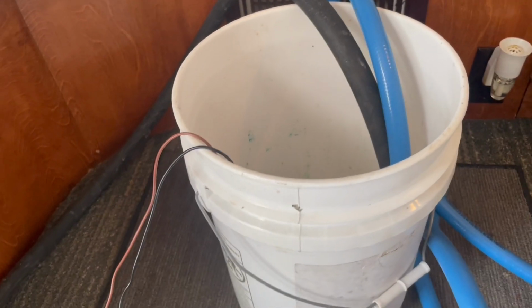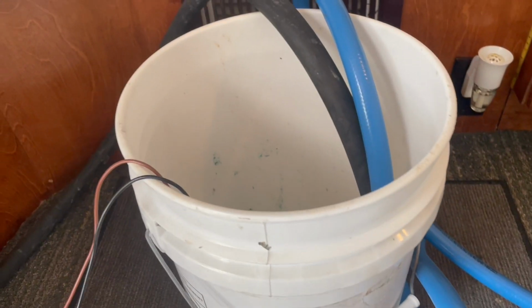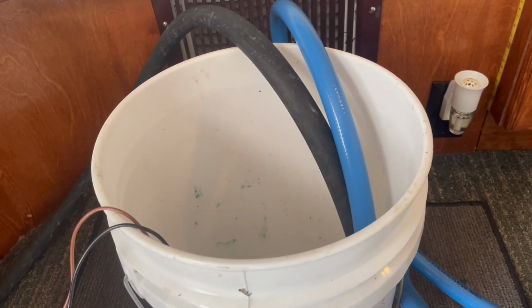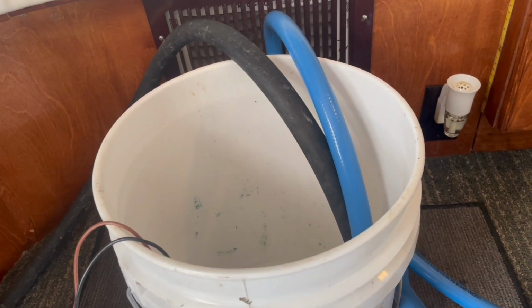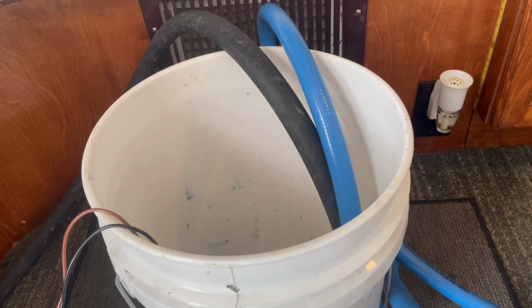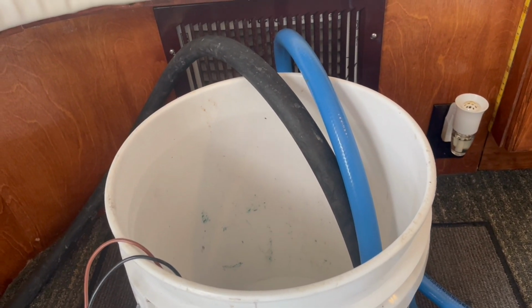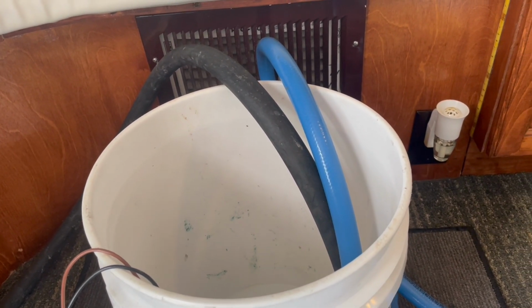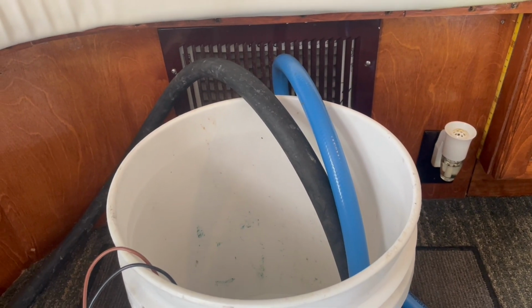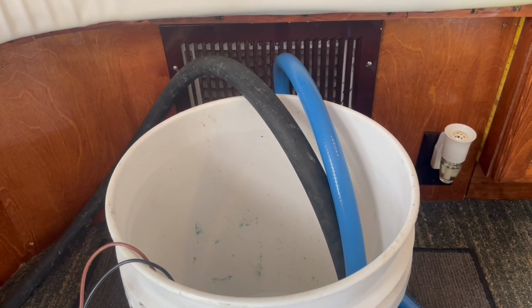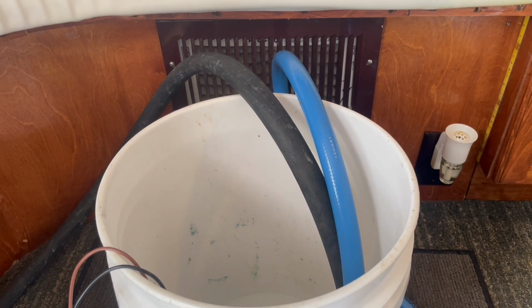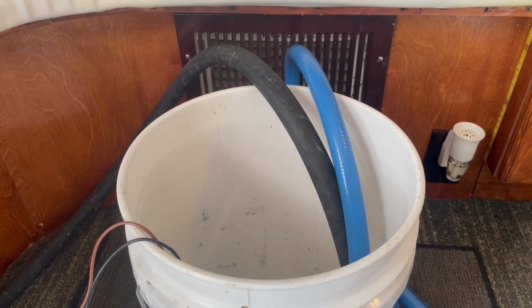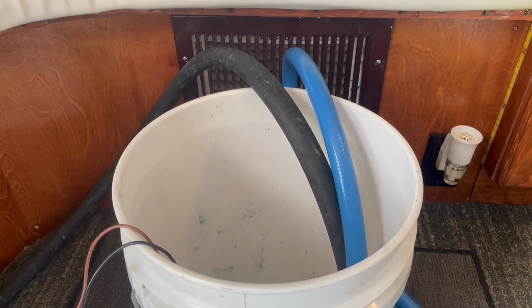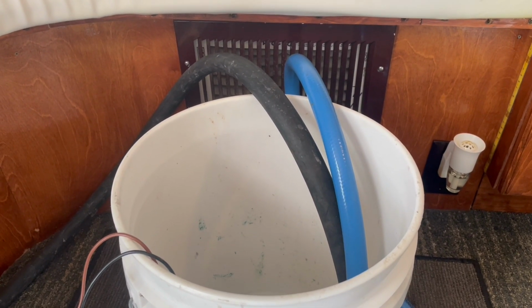Okay, so we're in the salon here, and I'm going to put my acid solution in this bucket. The reason the bucket's up here is you want the bucket higher than your heat exchanger. The one thing that'll keep this from working properly is if you get air in your heat exchanger - you can have a little air, but the more air you have, the less your coils get cleaned, because the air gets trapped in there and doesn't allow the water to touch everything.